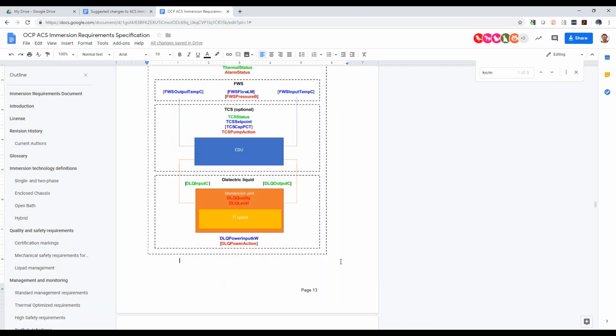So if you go into the FWS, the facility water system, you have an array - if there's any block, parenthesis around it, it means it's an array, so there could be multiple. Any input temperature and output temperature for the facility water should be noted if you have a thermally optimized system. For safety, you should have a pressure measurement available for each facility water system. That's the idea of how it's written down.